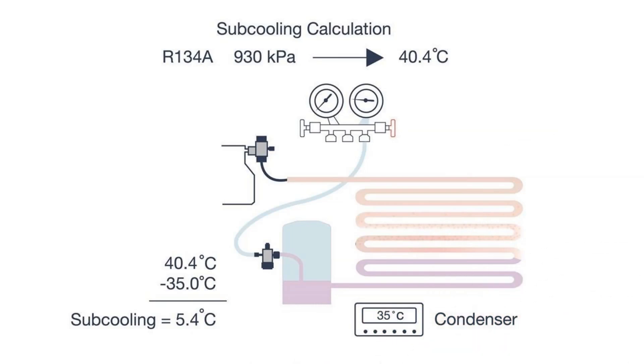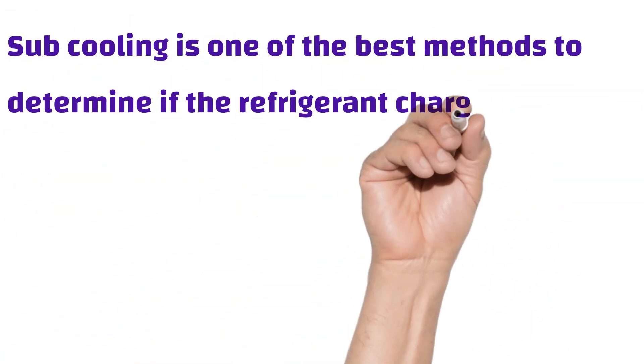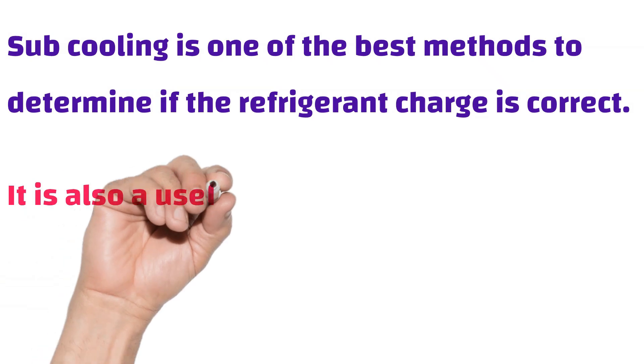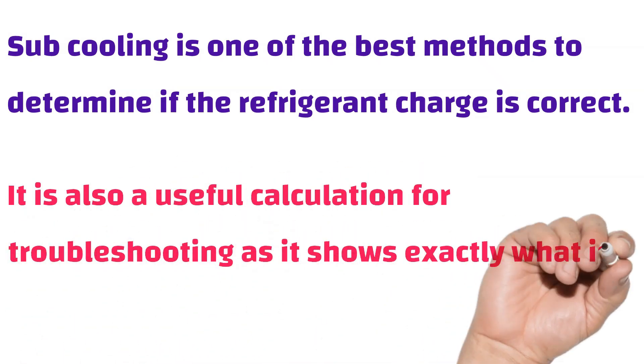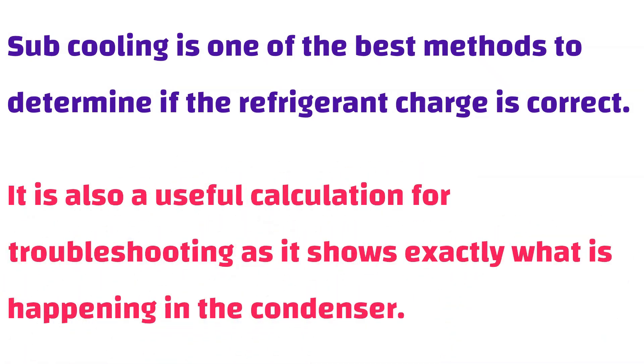Here is a sample example for how to calculate sub-cooling. Sub-cooling is one of the best methods to determine if the refrigerant charge is correct. It is also a useful calculation for troubleshooting, as it shows exactly what is happening in the condenser.